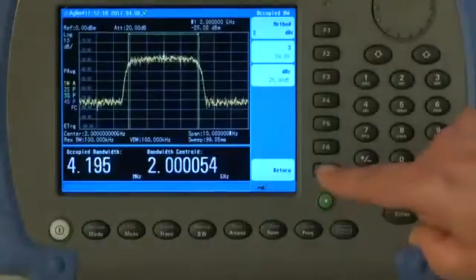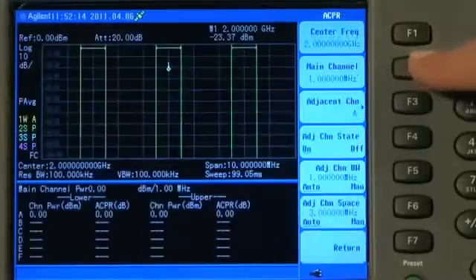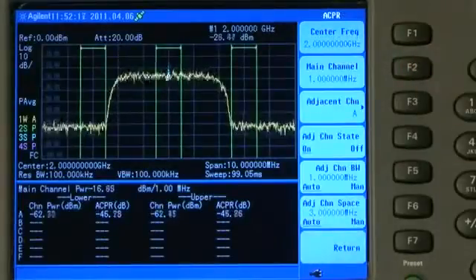If I press the return soft key, you can see there is another useful measurement here called adjacent channel power, ACP. Now here, of course, we are going to need to set up the channel bandwidth.